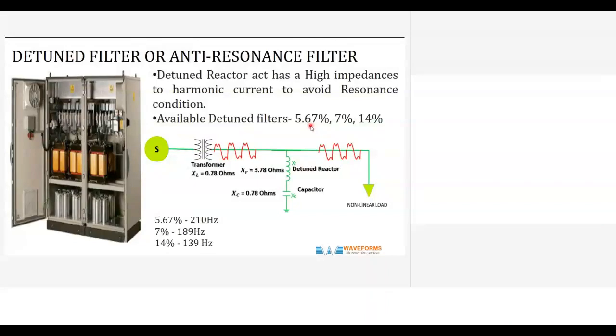Okay. So normally, in most cases they use a detuned filter or anti-resonant filter along with your capacitor bank to prevent the amplification and magnification of the signals. So it depends on what harmonic is dominant in the network. Suppose it is the third harmonic, you normally use this 139 hertz reactor. We also call it a 14% impedance reactor. This blocks the third harmonic from flowing to the capacitor, and it prevents the resonance. Similarly, if the fifth and seventh harmonics are dominant, use a different type of reactor to block.